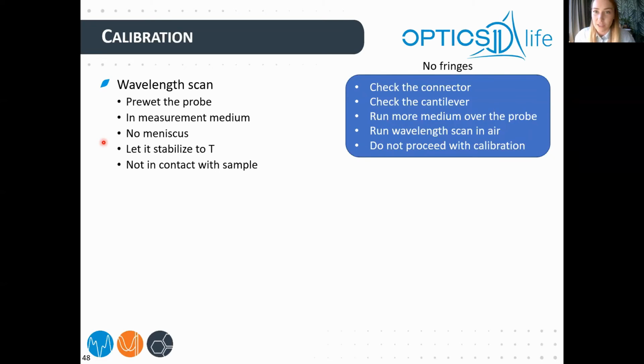If you don't get fringes after the wavelength scan, you need to check the connector. It might be that it didn't click in. You also need to check the cantilever. I usually just lift the probe up, run some liquid over it, and put it back into the medium, and then try again. Maybe it was just stuck, or there was an air bubble or something. So that's a very quick test. You can also run more medium over the probe when the probe is already in liquid, which makes a flow over it. If something got stuck when it was entering the medium, this is going to help.